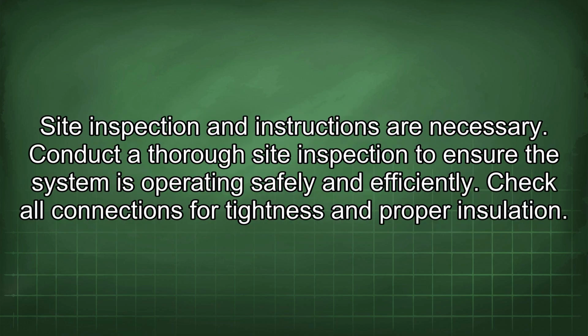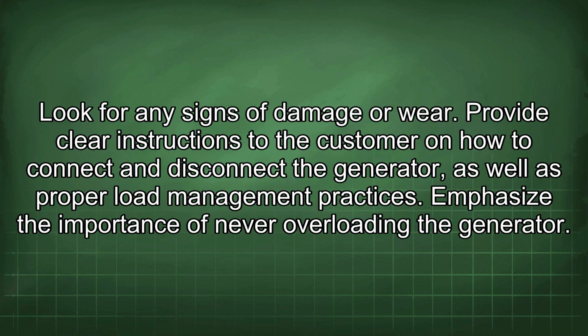This total amperage should be less than the generator's rated amperage. Site inspection and instructions are necessary. Conduct a thorough site inspection to ensure the system is operating safely and efficiently. Check all connections for tightness and proper insulation. Look for any signs of damage or wear. Provide clear instructions to the customer on how to connect and disconnect the generator, as well as proper load management practices.